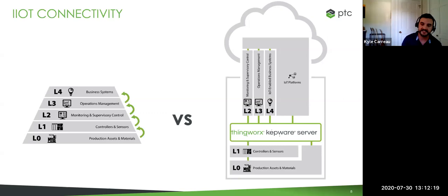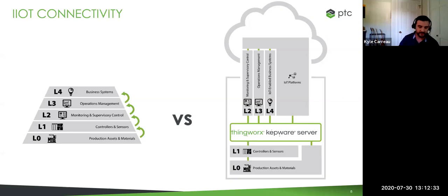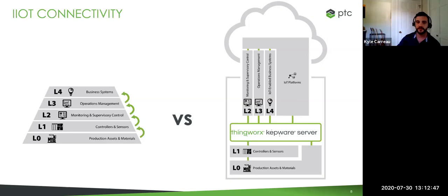What we've seen is more of what we call an elevator approach — some sort of middleware, in this case hopefully Kepware, between your PLCs and the rest of your applications. The idea is that middleware ingests data from your factory floor whether through Modbus, Ethernet, or whatever industrial protocol you have, then transforms that into things like MQTT, OPC-UA, REST, or ODBC connections — all from one central location — so you can send that data to different places without going through each step to reach your final end solution.